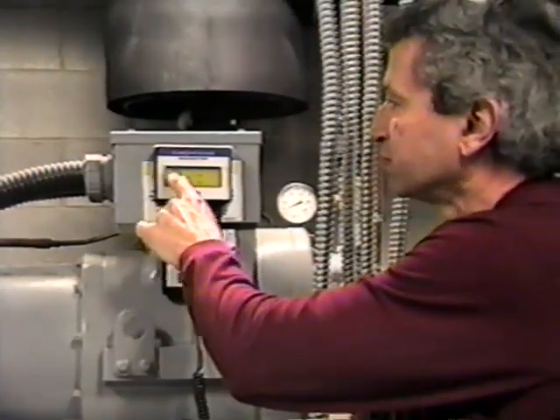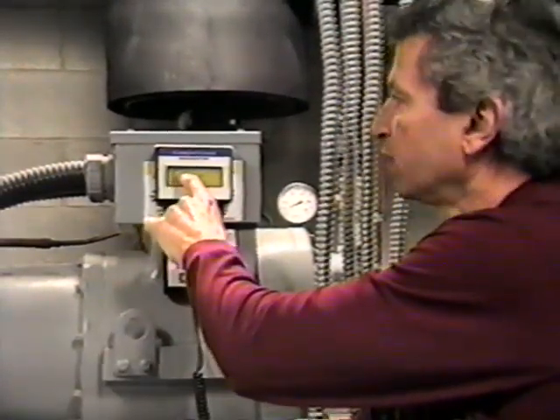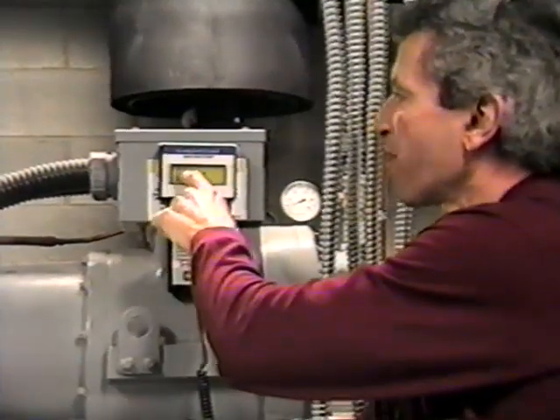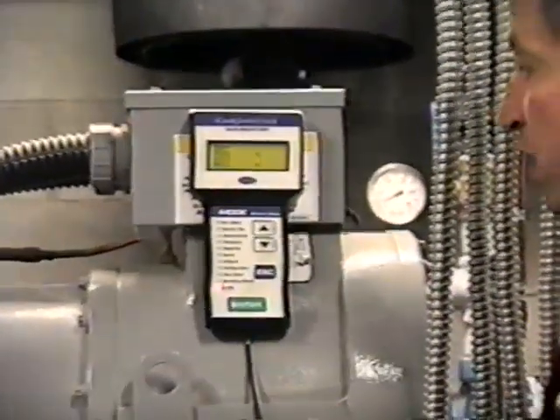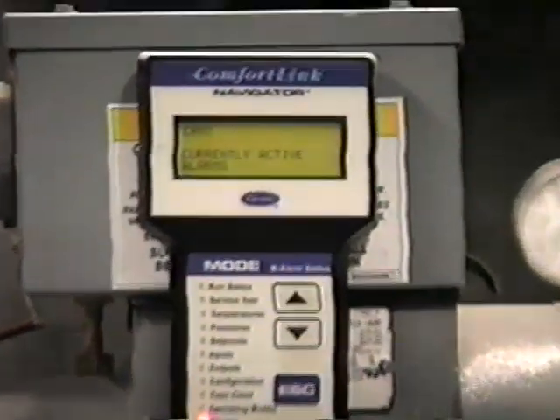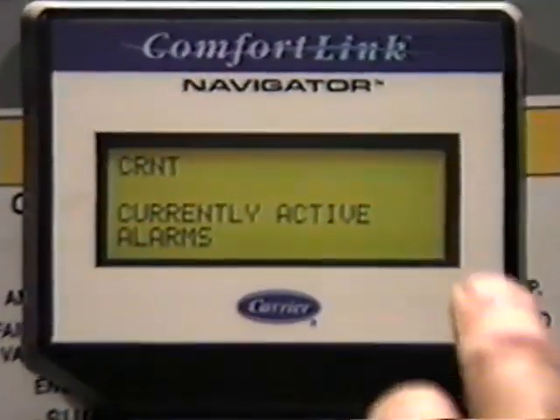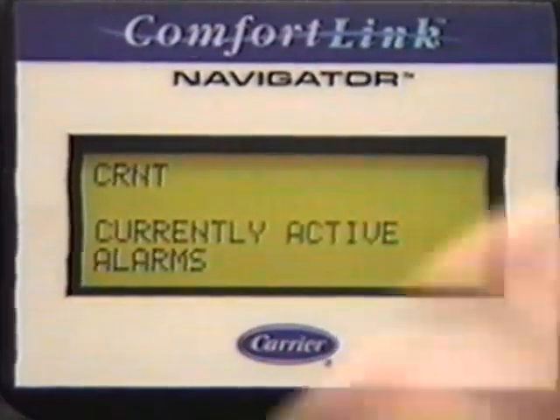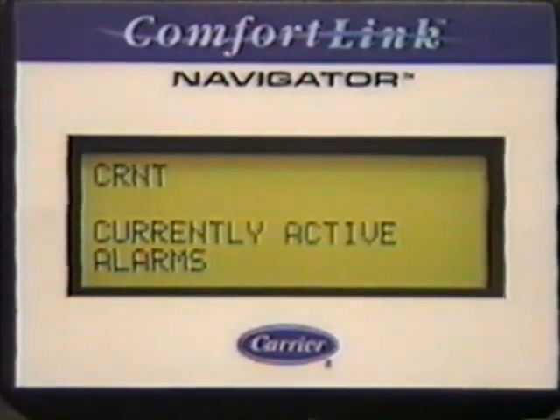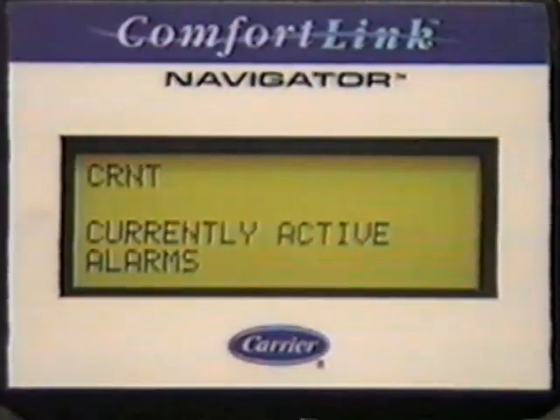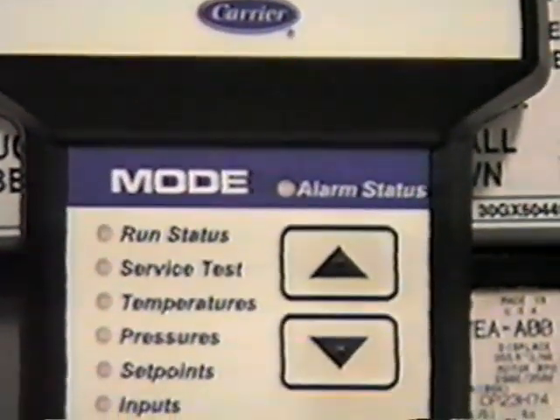In any case, if you do have an alert, it's going to show up on this first line, CRNT, and you can expand on that, and it'll say currently active alarms. Those are alarms that are still in that condition, which won't allow that circuit or that machine to run. We call them alarms here, but it could be an alert related to only the one circuit, or the total machine could be down. But if this light is blinking, you'll know it's an alert condition. One of the circuits is not healthy at that point.